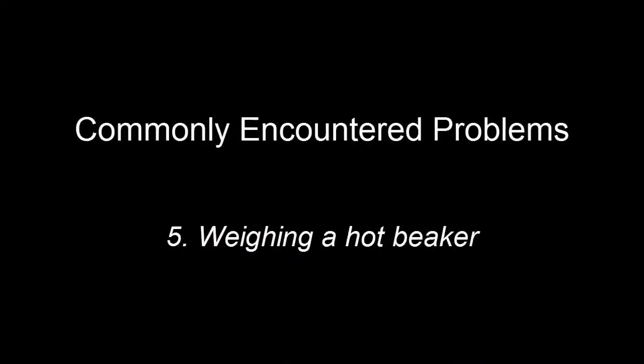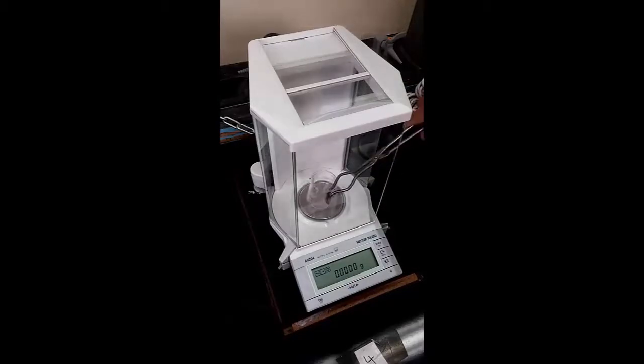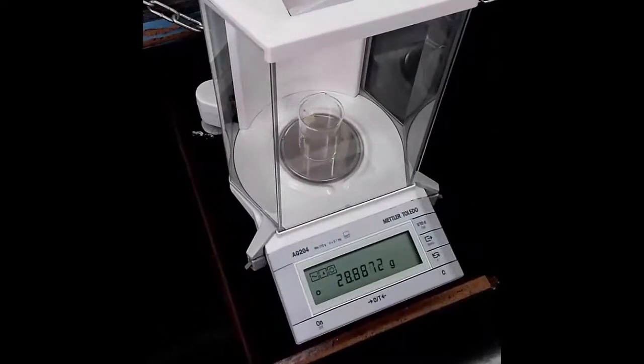5. Weighing a Hot Beaker. A hot beaker causes air currents with enough force to cause erratic balance readings. Always allow hot glassware to cool to room temperature prior to weighing.